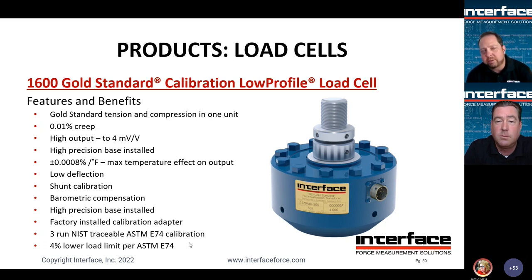And we've ensured now that there's no variability in terms of how the load introduction is presented to the load cell in terms of where the beams are and where the gauges are right below that top cover. So by us covering the fixturing element, we are delivering a product now that when you put it into your test case or into your frame, is going to have even better uncertainty and improved repeatability. So that's the really important spec you want to be looking for and be thinking about when you're characterizing your own standards: what is repeatability or reproducibility.